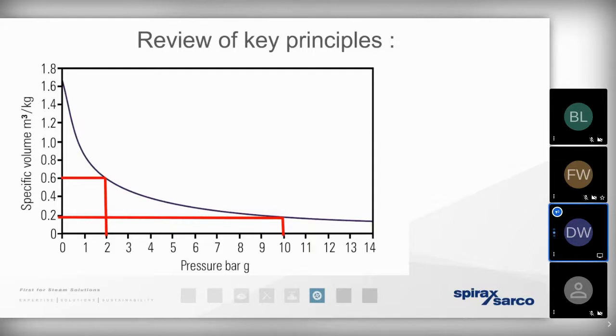Simply put, because there's as much heat energy present within that flash steam, we either want to find a way to minimize the creation of that flash steam or identify a way that it can be reused. Simply put, a fall in condensate pressure will result in that flash steam. So now we understand the basic principles.